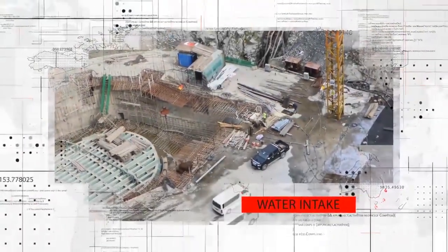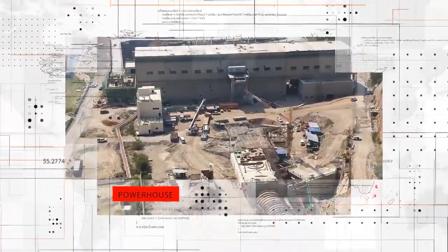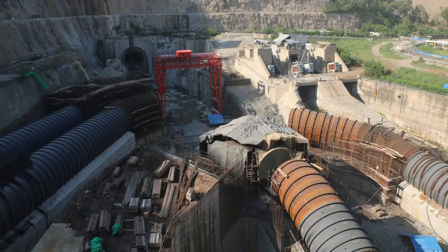The modified intake structures are hydraulically designed to divert the flow of water into the new shafts which are connected down to the existing tunnels. The overall length of Tarbela 4th powerhouse is 136 meters, width of the superstructure as well as inlet weld block is 28 and 13 meters respectively. The depth from ground level to foundation is 44 meters whereas its height above ground level is 29 meters.